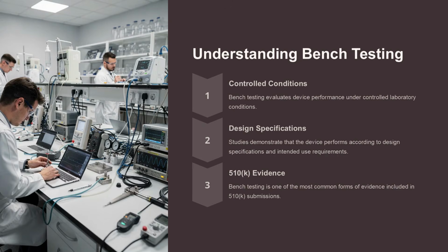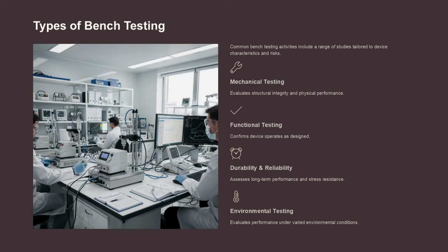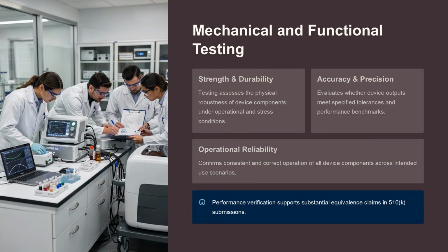Bench testing evaluates device performance under controlled conditions, ensuring compliance with design specifications and supporting 510(k) submissions. Bench testing includes mechanical, functional, durability, and environmental testing to ensure devices meet performance standards under various conditions. Mechanical and functional testing assess the strength, accuracy, and reliability of device components, supporting substantial equivalence claims in 510(k) submissions.